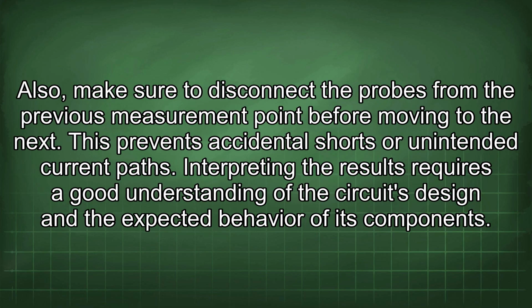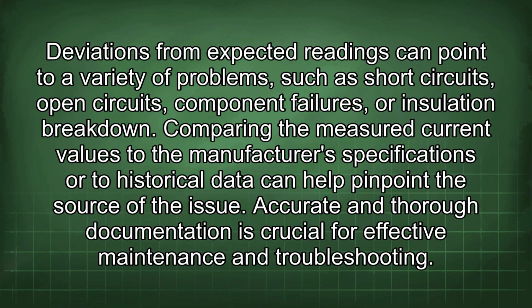Also, make sure to disconnect the probes from the previous measurement point before moving to the next. This prevents accidental shorts or unintended current paths. Interpreting the results requires a good understanding of the circuit's design and the expected behavior of its components. Deviations from expected readings can point to a variety of problems such as short circuits, open circuits, component failures, or insulation breakdown.